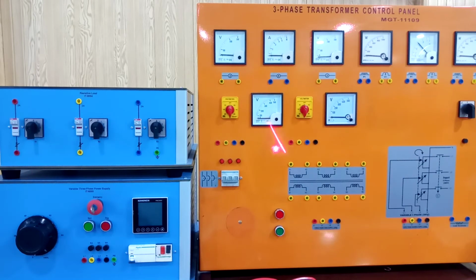This is our three-phase transformer control panel. There are a few voltmeters, an ammeter, a wattmeter, a power factor meter, and another wattmeter. We also have multiple voltmeters with selector switches, which let you connect multiple phases plus a neutral and select which phase or neutral to display on the voltmeter. This saves a lot of panel space when working in industry or on commercial projects.